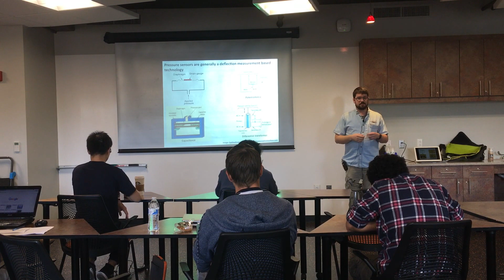There's a variety of ways these work internally. One of the most common is that you've got a diaphragm, and the applied pressure deforms that diaphragm. There's a strain gauge on it, which you can calibrate to the pressure. Similarly, you can have a potentiometer, a variable resistor like the one you used on Thursday, that changes its resistance based on how much the diaphragm is deformed. You can also do a capacitance measurement, a capacitive distance sensor with pressure applied to one side. Or it can be a differential transformer setup, like the LVDT. All of these are measuring the deformation of a diaphragm. A diaphragm is generally made from some very resilient, corrosion-resistant material, so these are not cheap generally. $700 to $1,000 would be a pretty standard figure for a run-of-the-mill transducer.